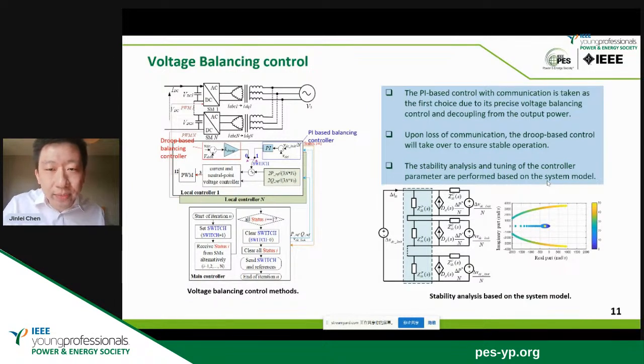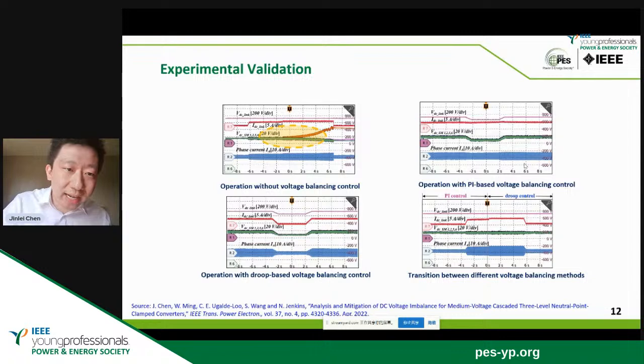controller. However, upon loss of this communication, the PI-based control is out of use because it's dependent on the communication. So upon the loss of communication, it will switch to the droop-based balancing controller, to ensure the continuous operation of the system. And I also developed the small signal model for the system stability analysis and the controller parameter tuning.